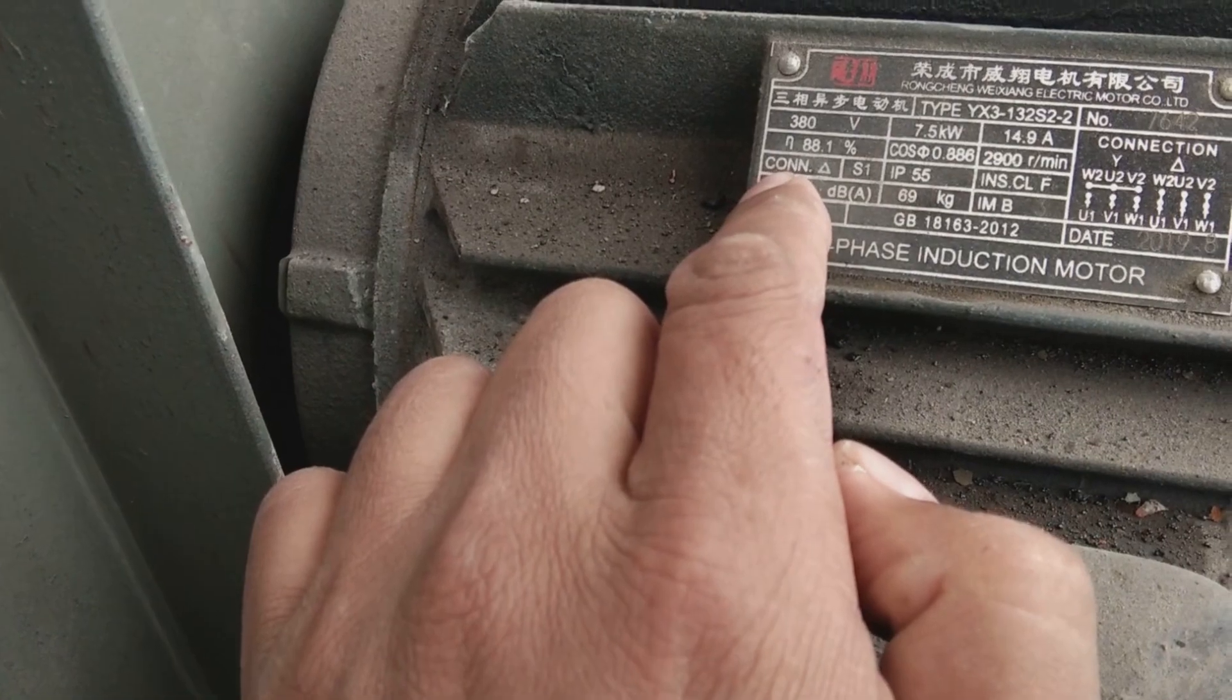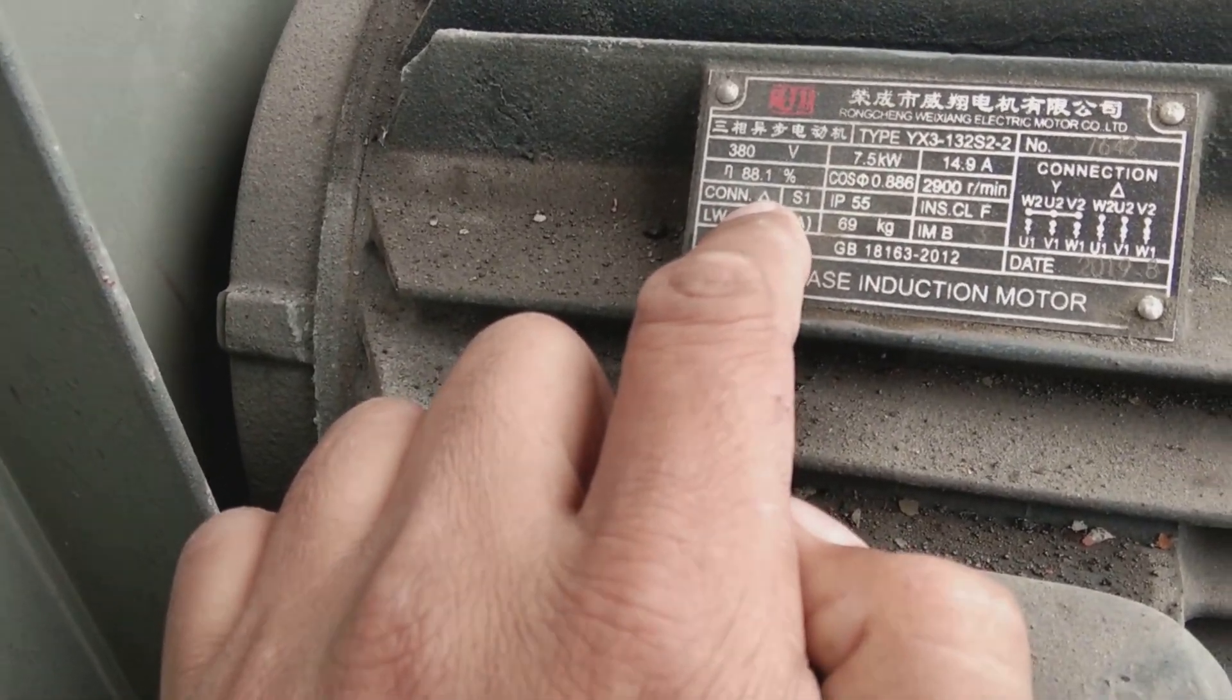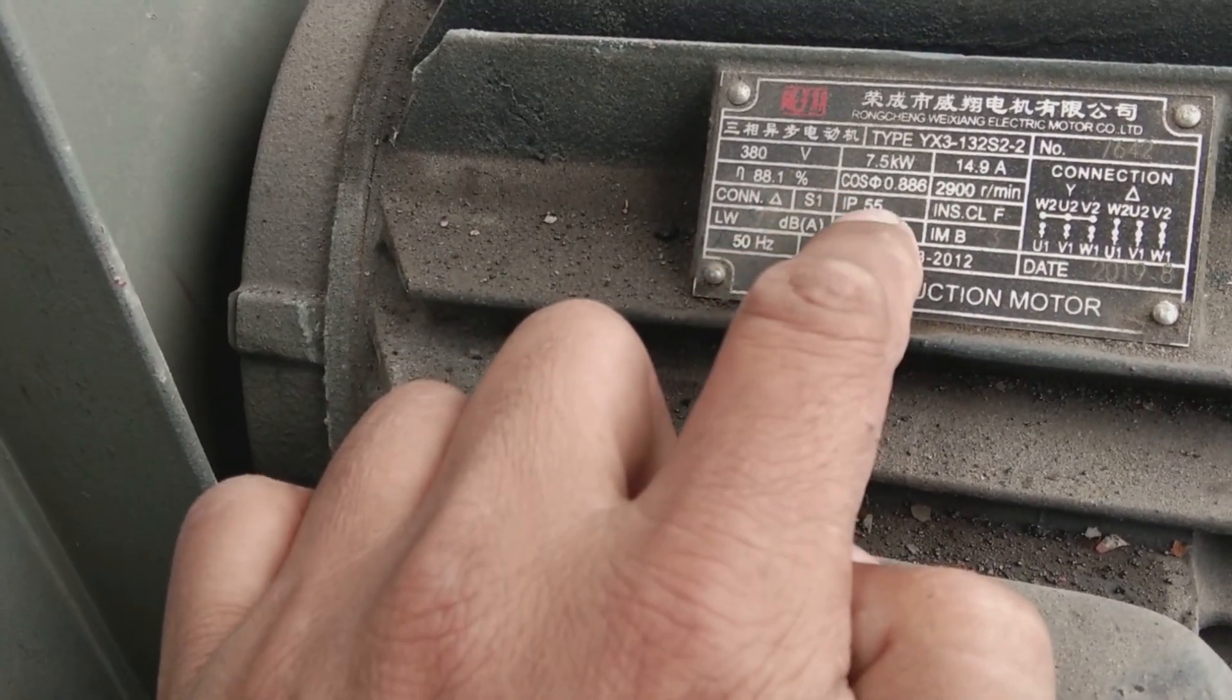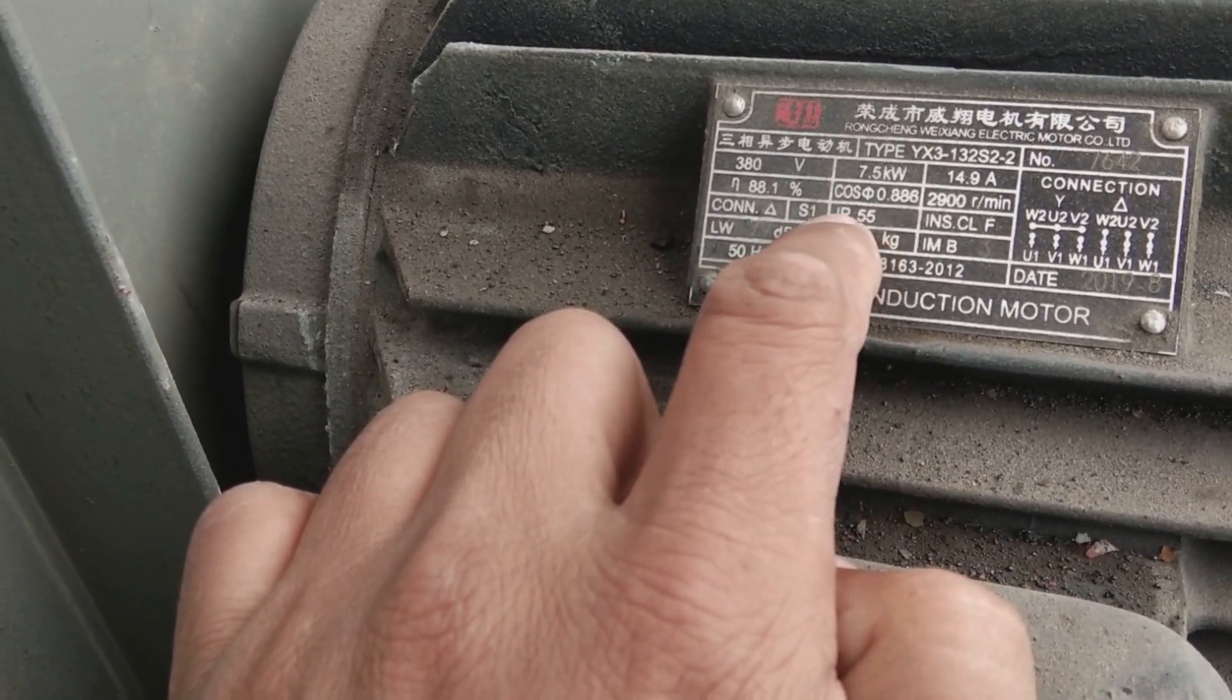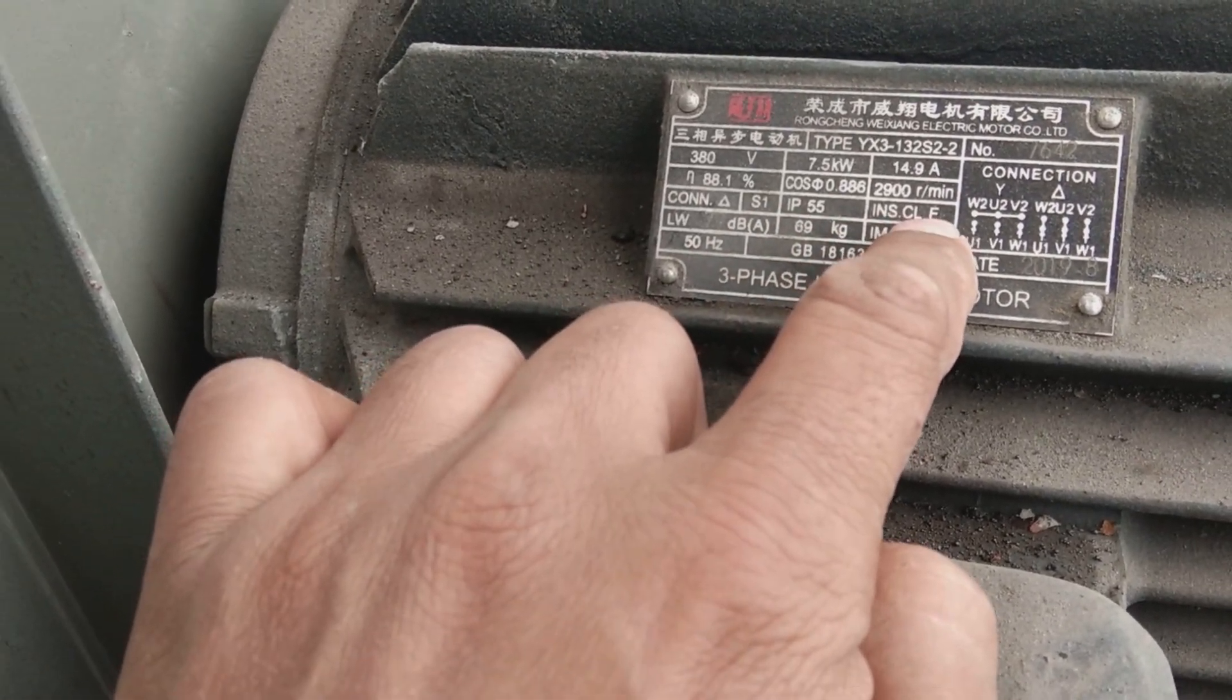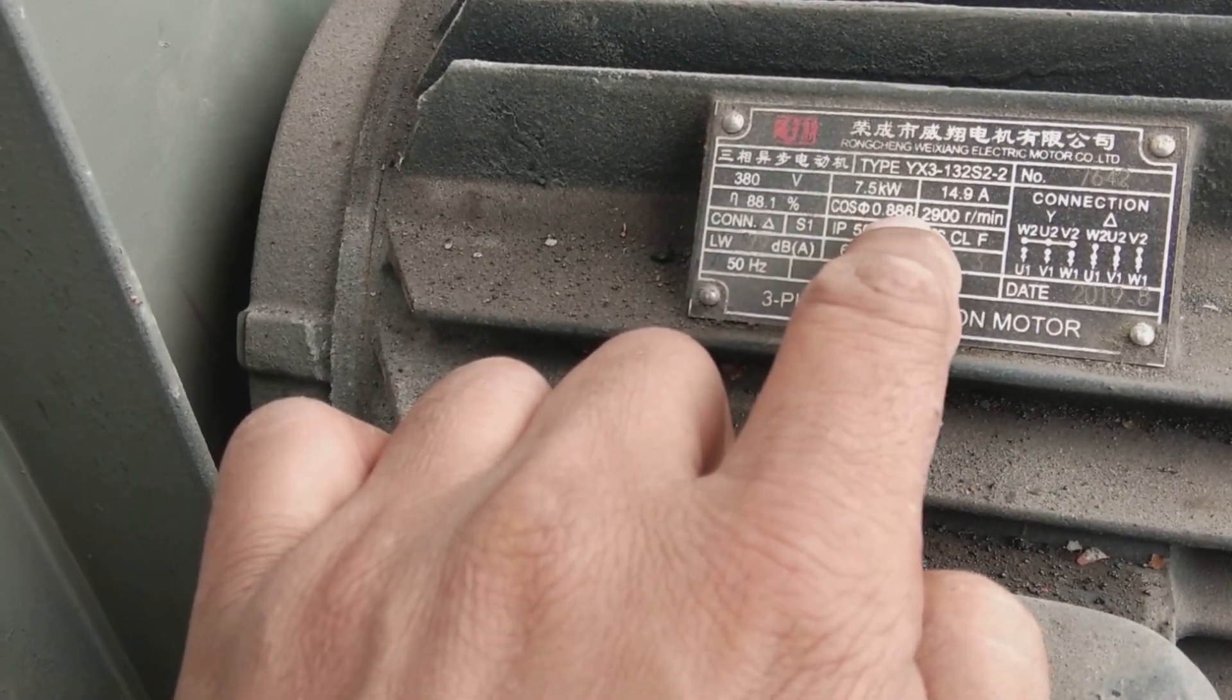This is delta connected as written here. This is S1 duty cycle motor with ingress protection IP55. Insulation class is F, and 2900 is the RPM. The power factor, cos phi, is 0.886, which is a better power factor for this motor.